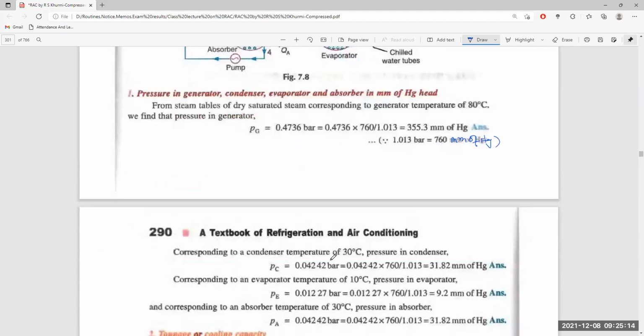Pressure in the condenser, temperature is 30 degrees centigrade. From the steam table the pressure is 0.04242 bar. Multiplied by 760 by 1.013 using this formula, the pressure in the condenser is 31.82 millimeter Hg.